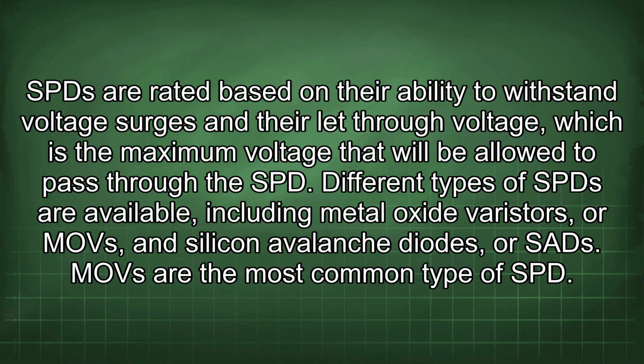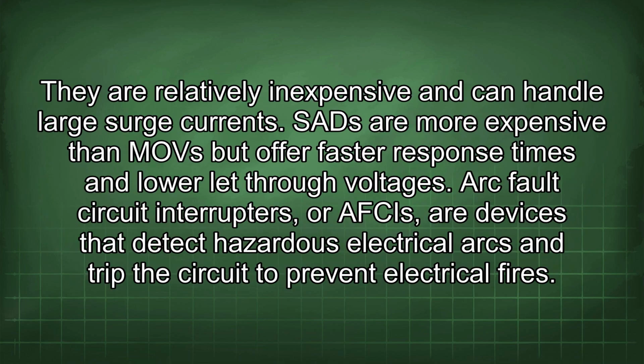Different types of SPDs are available, including metal oxide varistors, or MOVs, and silicon avalanche diodes, or SADs. MOVs are the most common type of SPD. They are relatively inexpensive and can handle large surge currents. SADs are more expensive than MOVs but offer faster response times and lower let-through voltages.